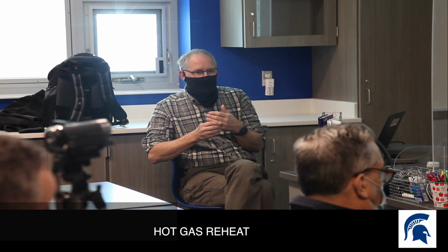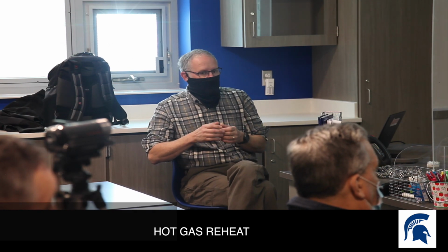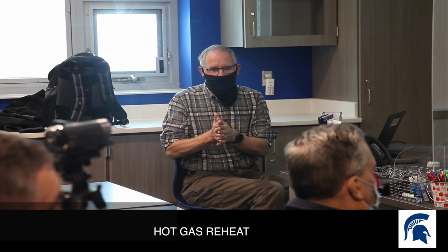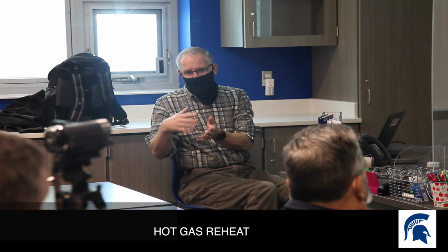No, this is, okay. You probably only see the gas heat run during the winter, okay, because you've got hot gas reheat, right? So, and then you have belts on the exhaust fan and belts on the supply fan, right, on the bigger unit. Yes. We're gonna grab one or two of those up on the roof and we'll take a peek at them, okay? So everybody kind of understand how hot gas reheat works, okay? Now, I don't know how deep your guys gonna get into this stuff. If you're strictly maintenance and operation, you'll never have to worry about that. You'll probably be first responders who say, something's wrong, I gotta call somebody.